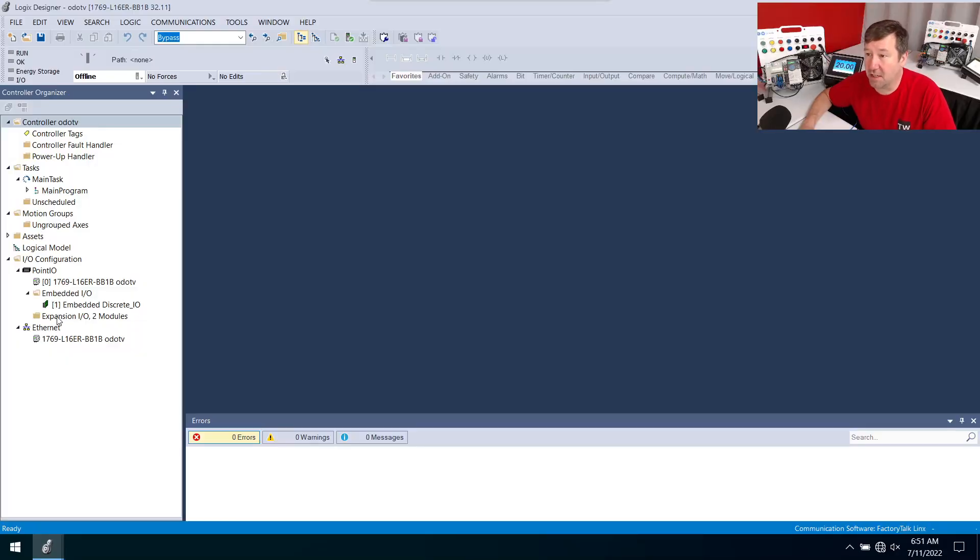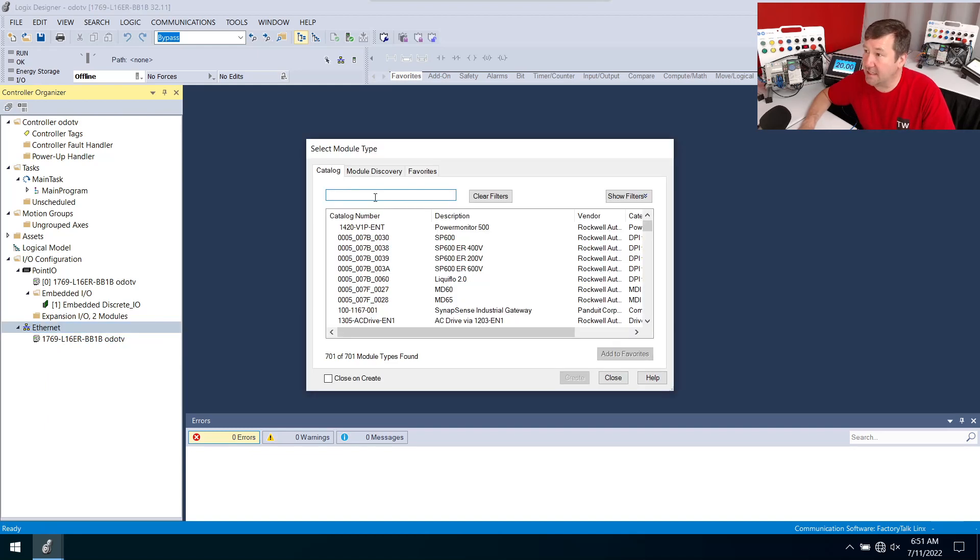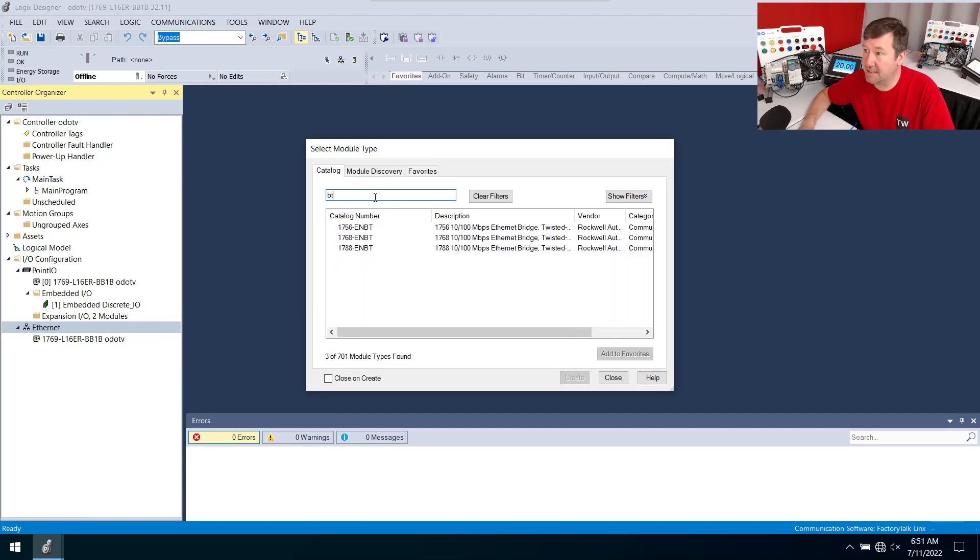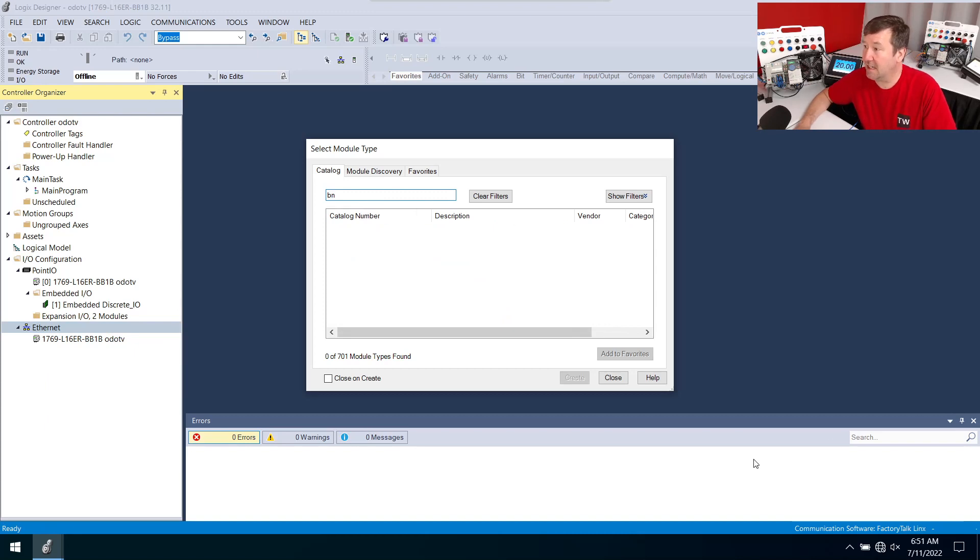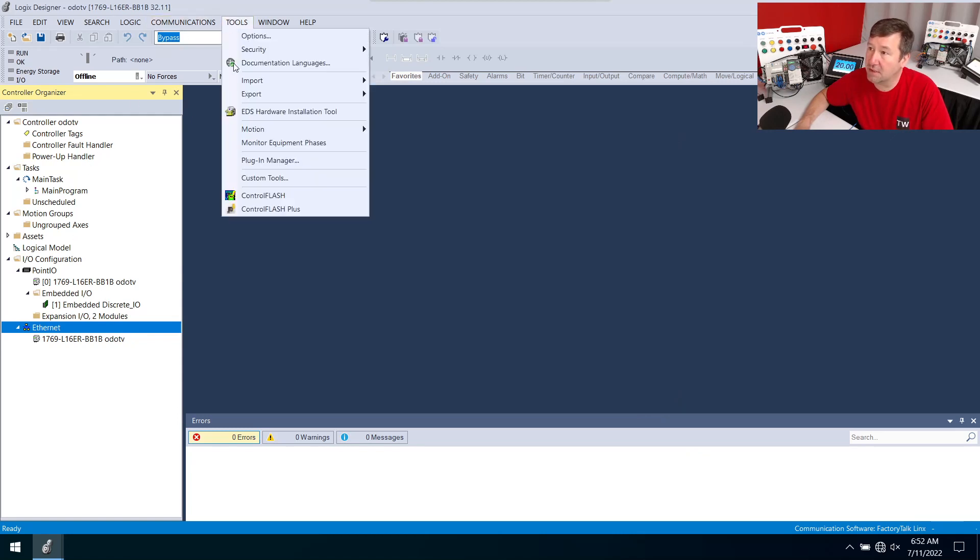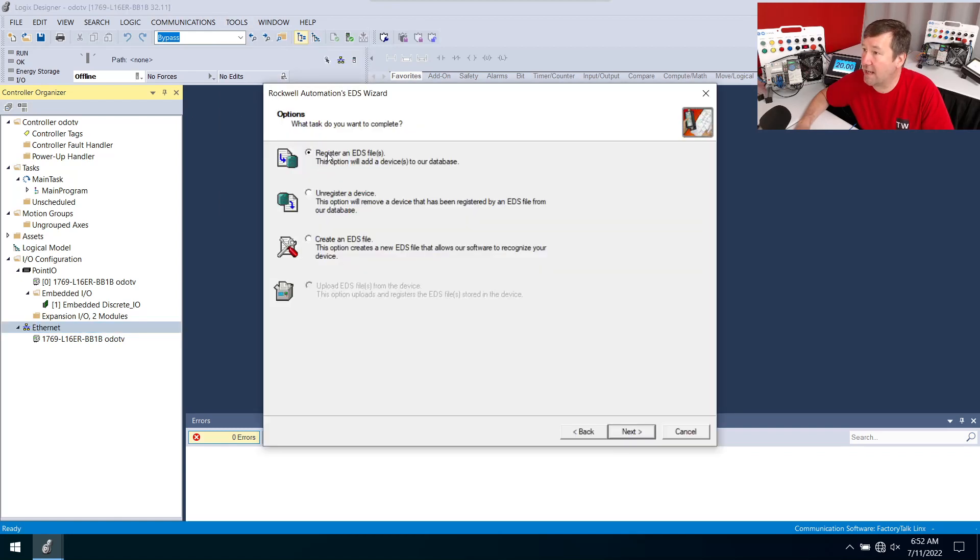If we're adding a device over ethernet we typically right click new module and then in here we type the model number which in this case starts with a BN and we get nothing. So we're going to have to add the EDS file. You can get them online but I've already downloaded it so we're going to go to tools and then EDS hardware installation tool and then we're going to register an EDS file next.